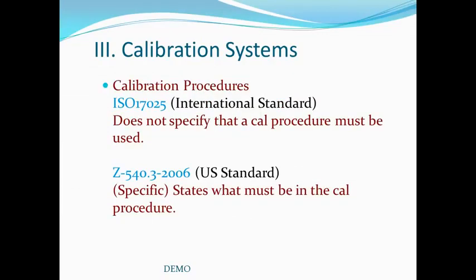Calibration procedures may have specific requirements if a lab is accredited to one of the documentary standards ISO/IEC 17025 or the Z540.3. Document 17025 does not use the words calibration procedure, but states that you need a procedure or method to assure equipment meets proper specifications for intended use. The language of Z540 is more specific, not only expressing the use of a calibration procedure, but names the elements that it should contain.